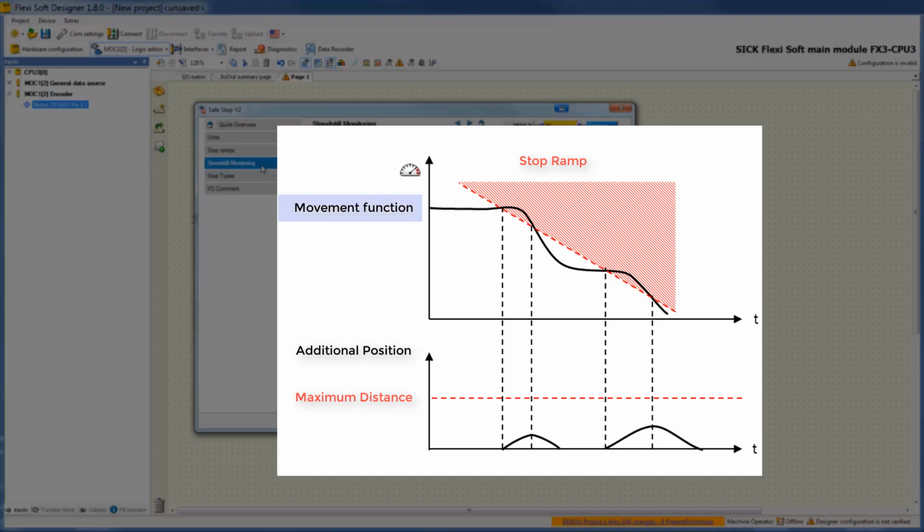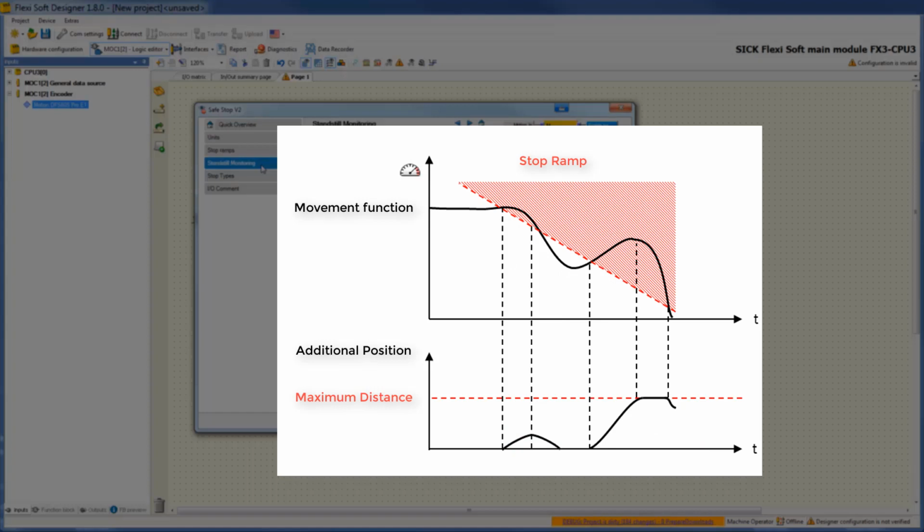There, you can see the movement of the drive, the stop ramp and the defined maximum distance for speed filter. At these points, the drive is moving in a forbidden speed. In this case, we calculate the additional position movement the drive is making in the forbidden area. Because it didn't exceed the maximum distance, there is no reason for shutting down the torque of the drive. If the maximum distance is exceeded, as you can see there, then the drive has moved too long distances while driving in a forbidden speed.